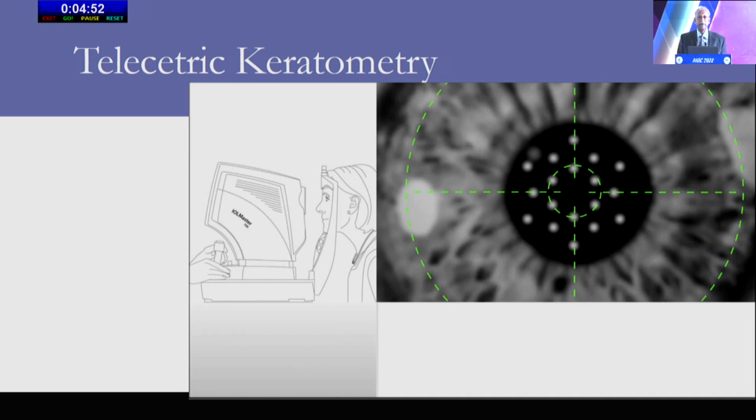It does give you better results on K values than any manual keratometer, since this looks at different zones. Depending on which machine you're using, it can look at a zone from 1.5 millimeters right up to 3.6 millimeters. So you get a true K value, which is very, very accurate. SSOCT-based optical biometers can also do a scan of the cornea and look at the posterior corneal curvature and know the posterior corneal curvature also. Since you get both of these parameters and values, the machine can calculate true K, which is very important for some of the more advanced formulae that we use.